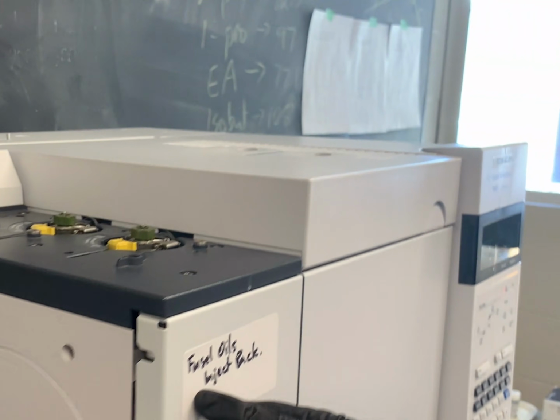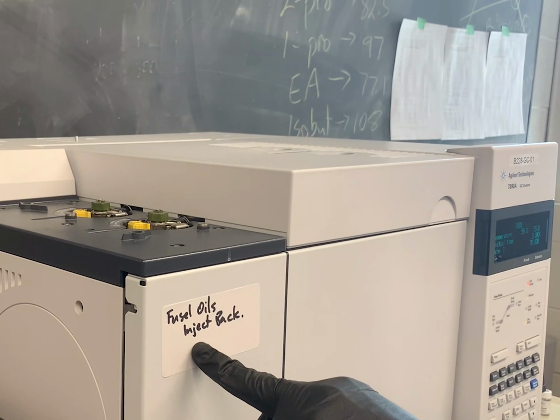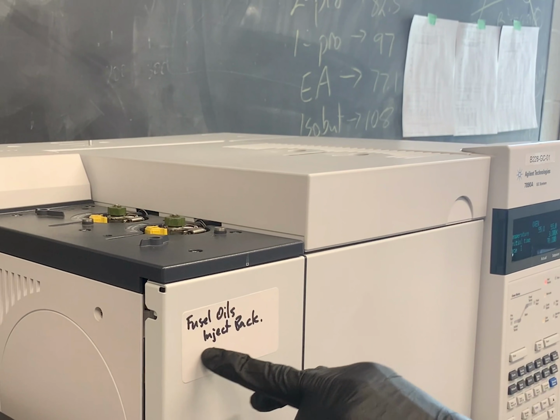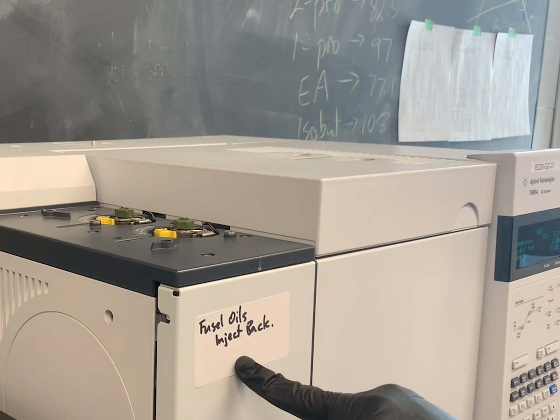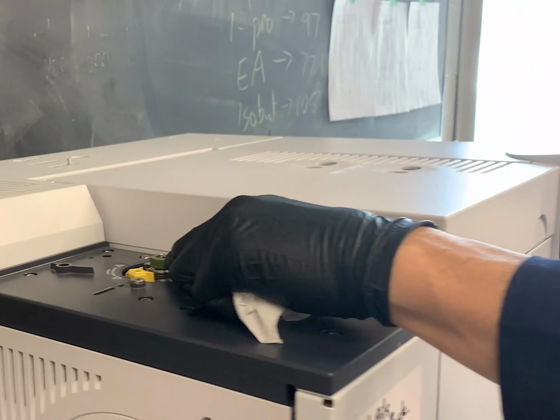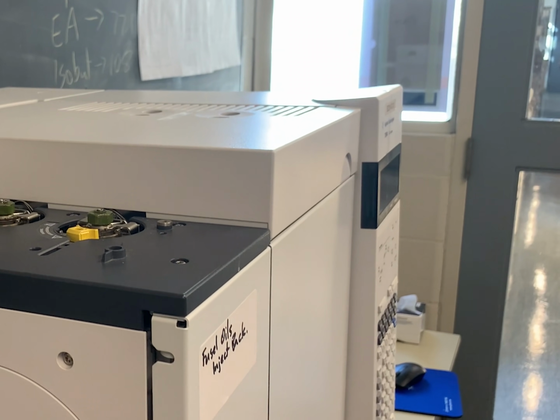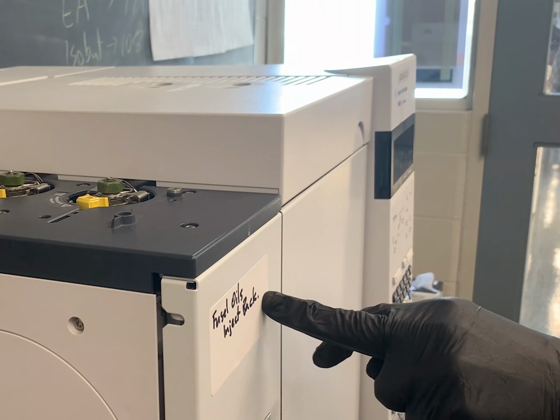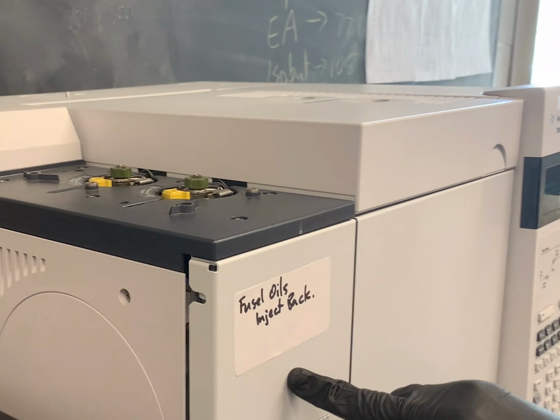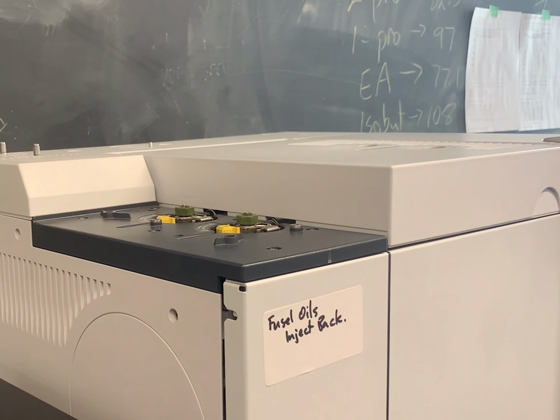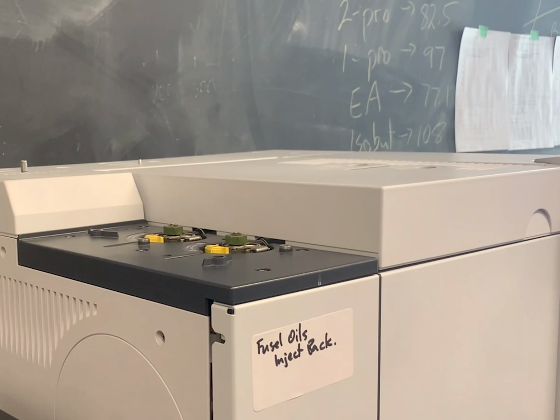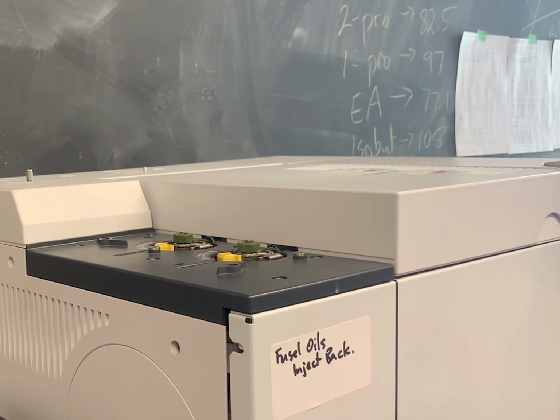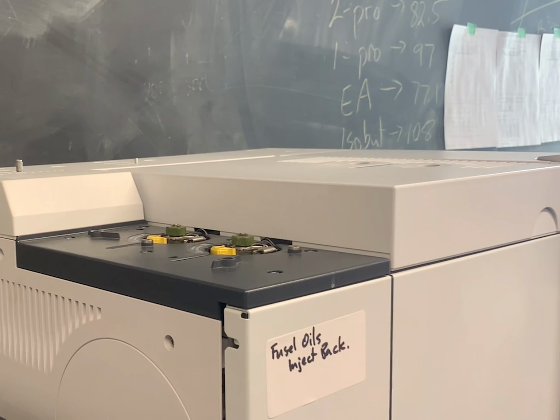And on the GC, it will tell you where to do your injections. On this particular model, we can only inject fusel oil in the back port. On some of the other GCs, the fusel oils will be in the back, the citrus will be in the front. So by convention, if you can do both on the GC, the citrus will be up in the front. The fusel oils will be in the back.